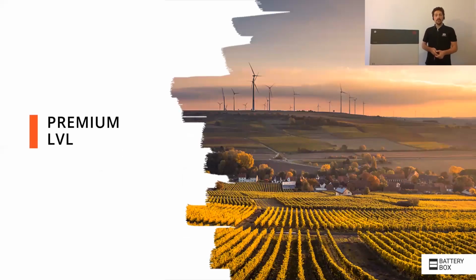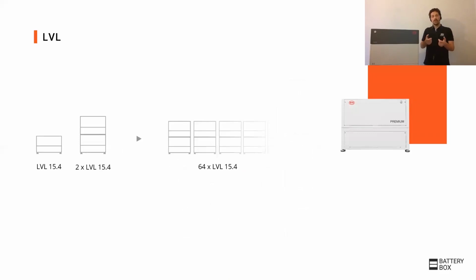So after looking at the high voltage systems, we will look at the 48-volt system, starting with the LVL, which stands for low voltage large. And the name refers again to the capacity. It's 15.4 kilowatt hours per battery cabinet, which is also the minimum capacity for the LVL systems. The capacity can be chosen individually from 15.4 kilowatt hours or in 15.4 kilowatt hour steps up to 64 LVL in parallel, which would be a capacity of 980 kilowatt hours, so nearly 1 megawatt hour. So you see with this system, it's extremely flexible to choose the capacity.